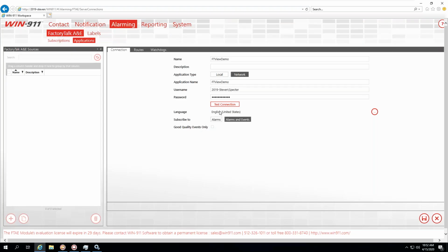A thing I didn't cover in my presentation is language switching. This is somewhat new. It used to be that WIN-911 always subscribed to the English alarm messages that were specified in FactoryTalk, even if you weren't using them. So for your description, you'd get something like "US English is not defined for this alarm." If you are not using US English, you can browse your application for the languages that are supported and choose which alarm messages you want to receive.